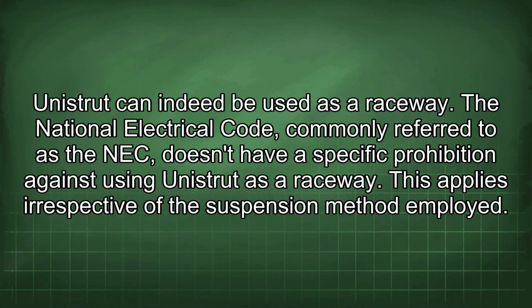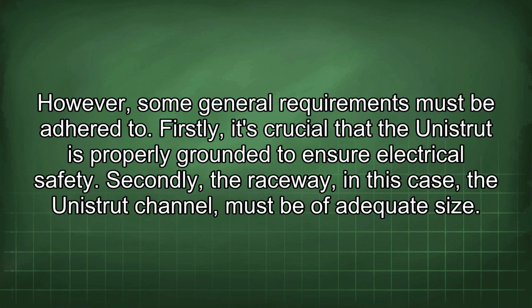Unistrut can indeed be used as a raceway. The National Electrical Code, commonly referred to as the NEC, doesn't have a specific prohibition against using Unistrut as a raceway. This applies irrespective of the suspension method employed. However, some general requirements must be adhered to.